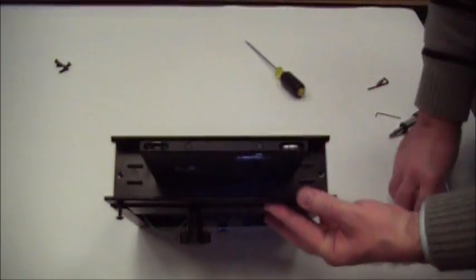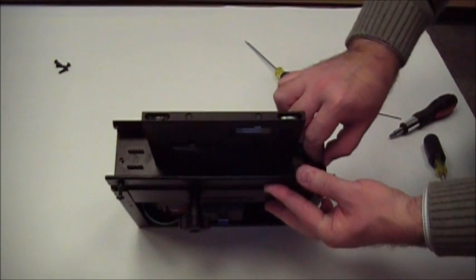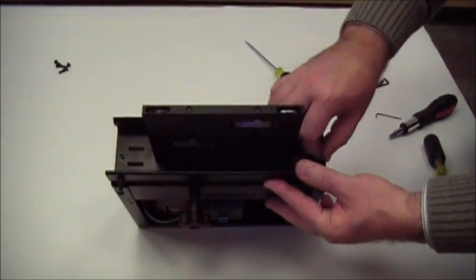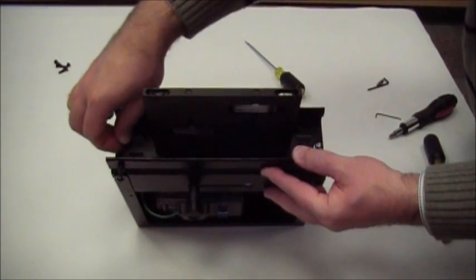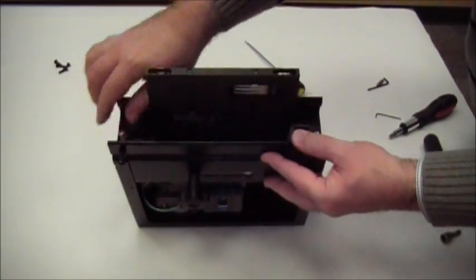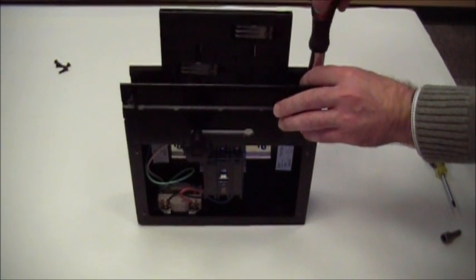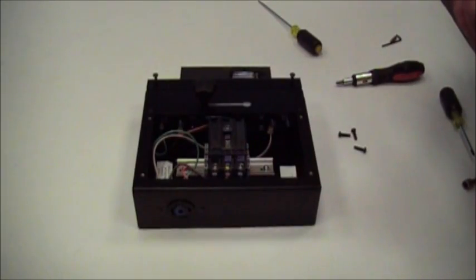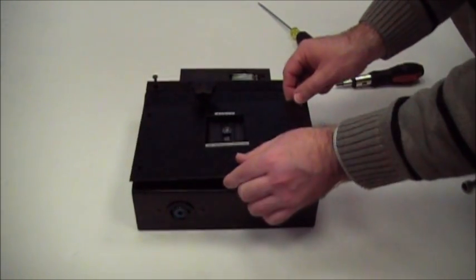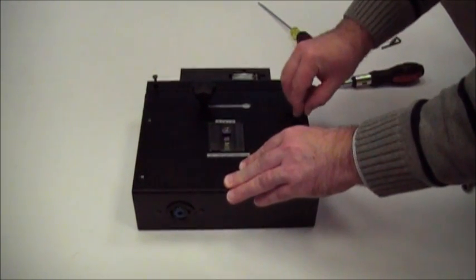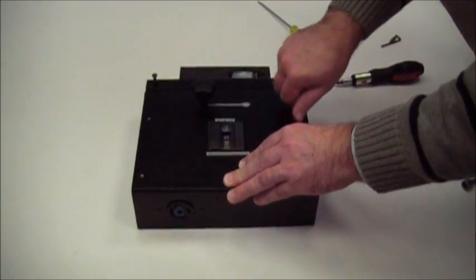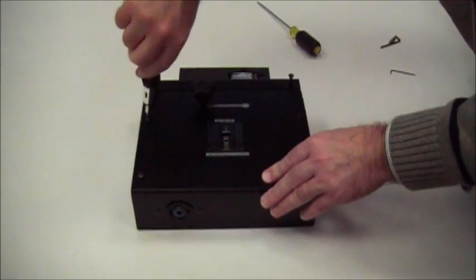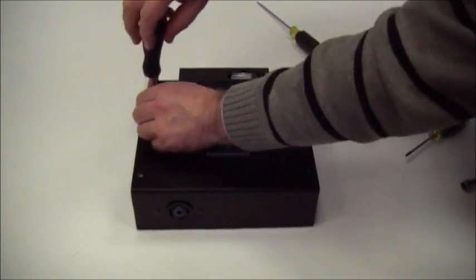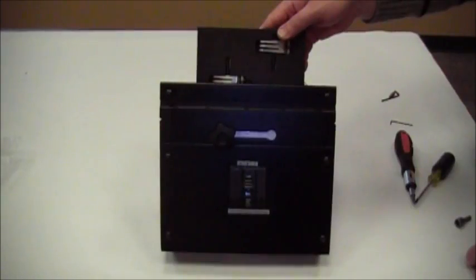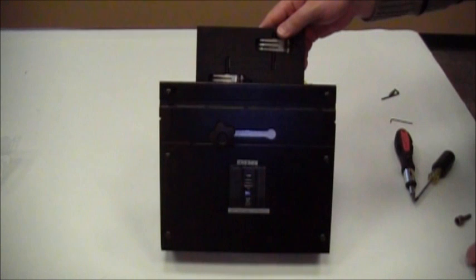Next we'll put the final two screws into the paddle assembly mechanism to hold that firmly in place. And then the last step will be to put the cover on over the breaker and secure it with 4 screws, and that will complete the assembly. And there we have the final bus plug for the Power Wave bus system completed.